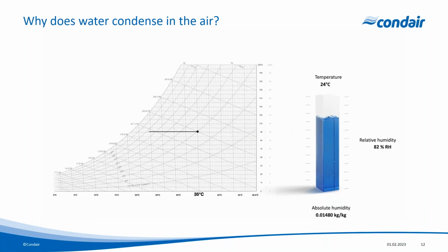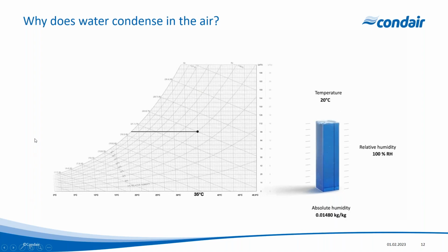When we sensibly cool the air, we see the effect is that we see a decrease in dry bulb temperature, but we see an increase in relative humidity. That's 50, 60, 70%, and so on. But the absolute moisture content is remaining the same. It's the capacity of the air to hold the water that is changing. So that's okay. We're cooling the air sensibly, but eventually we're going to reach a point where the air is 100% saturated.